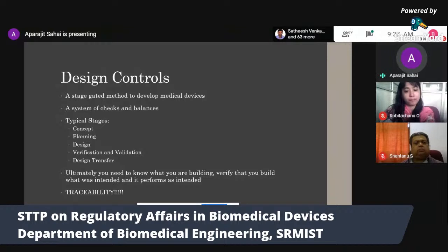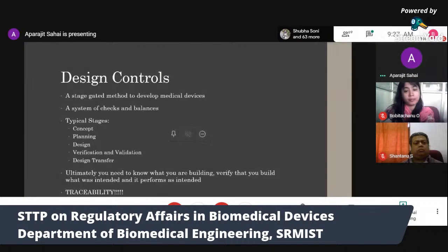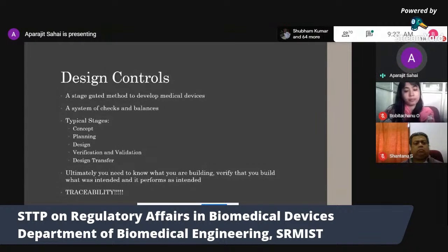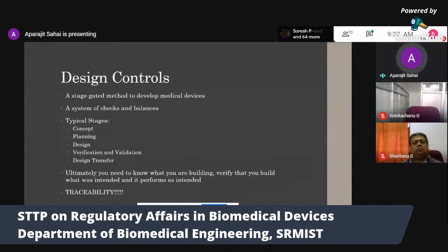in a particular market. So it could be a class 2 device in the US, it could be a class 3 in Canada, and that's totally possible because, for example, the device that we're developing at Flowsonics is a class 2 medical device in the US, a class 3 medical device in Canada, and a class 2A medical device in Europe. So it is quite possible that it has different classifications and may have to meet different requirements in different jurisdictions. So you plan for that. You have a regulatory plan, and you put everything into that regulatory plan. So the planning phase is essentially laying out the timeline, the goals, and all these things.